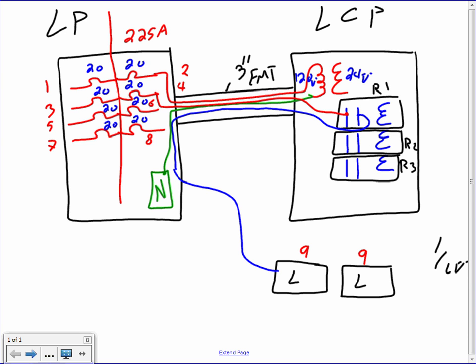Of course from here you jump to go to the second fixture, so these two sets of fixtures now have the hot coming to them. What do you need for the fixture to work too? Neutral. So grab the neutral, bring it here and here. Now these two fixtures have hot and neutral coming to them, and this will be your circuit.